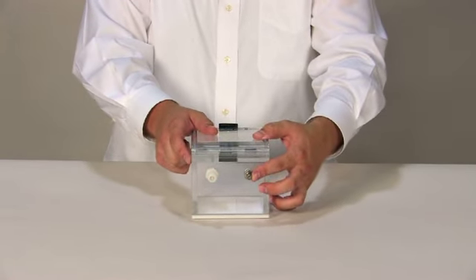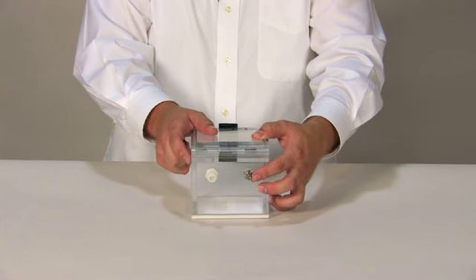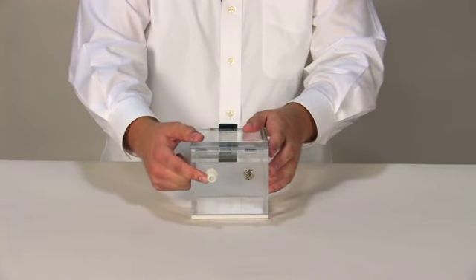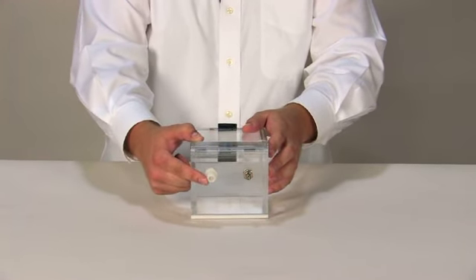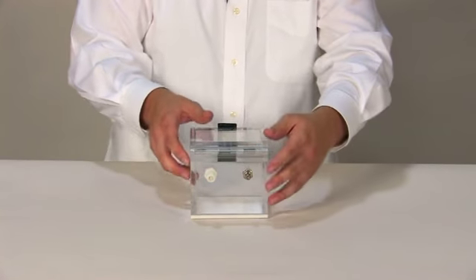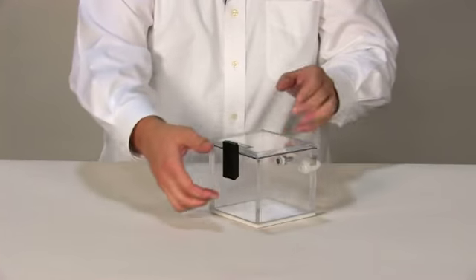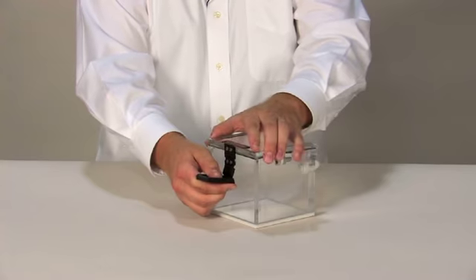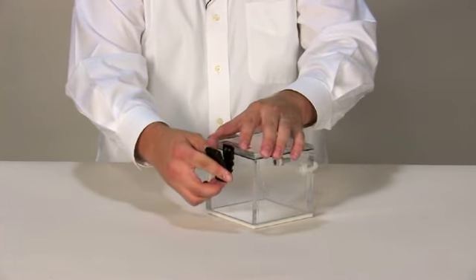The induction chamber receives anesthetic vapor from the anesthesia machine here and directs anesthetic vapor away from the chamber to a charcoal filter via this connection. The chamber is opened and closed using this draw latch on the front of the chamber.